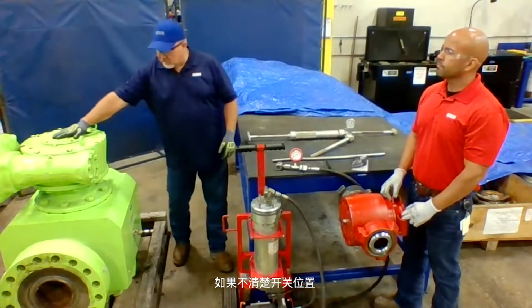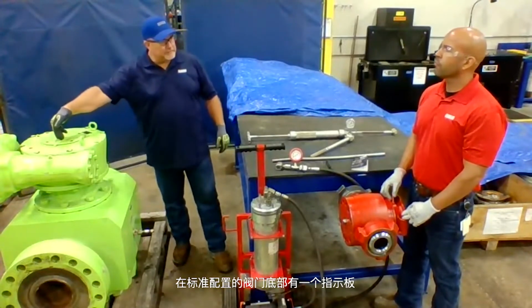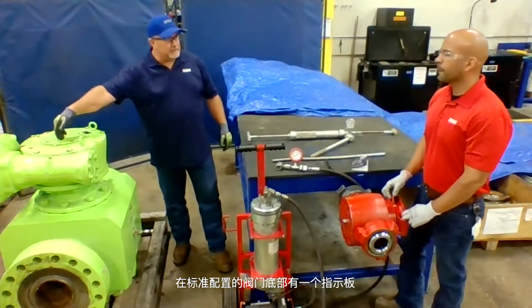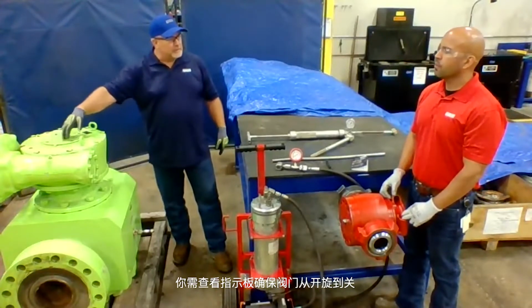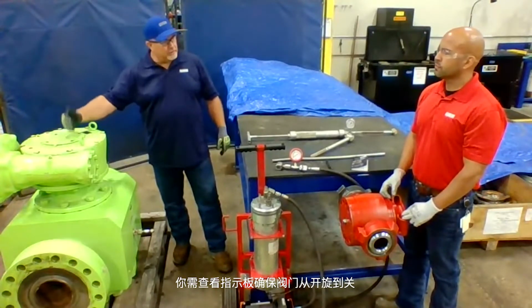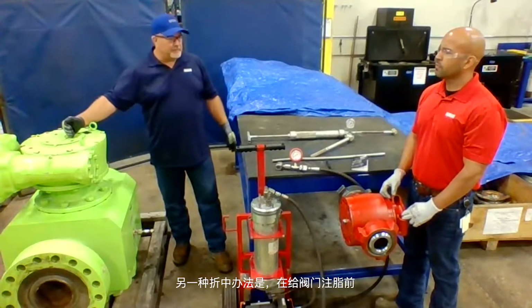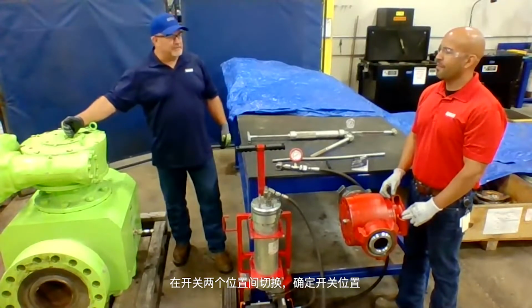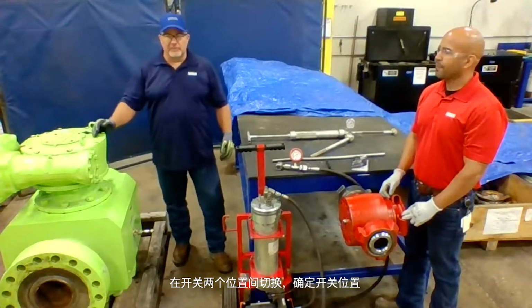If there's any confusion, there's an indicator plate on the bottom of the valve in the standard configuration. So you'll need to look to make sure that it went all the way from open to closed. Gotcha. Half measures don't grease the valve. Yeah, you have to go all the way to stop on both positions.